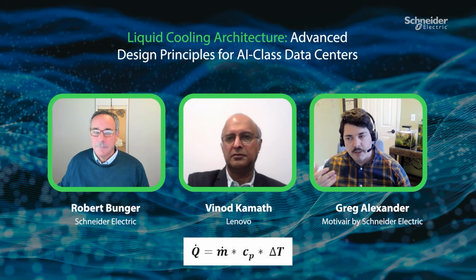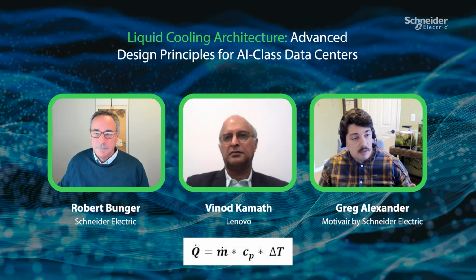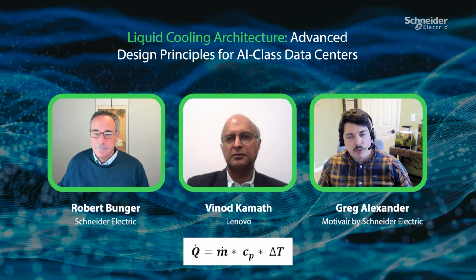So generally, let's say you have a 500-watt GPU—that's your Q, and that's fixed. Whether you cool it via liquid or air, air cooling will have lower mass flow and lower Cp, so the delta T is going to be a lot larger. Whereas with fluid, you have much higher mass flow rate and much higher specific heat capacity, so you can have a lower delta T. That just makes the whole system more efficient.